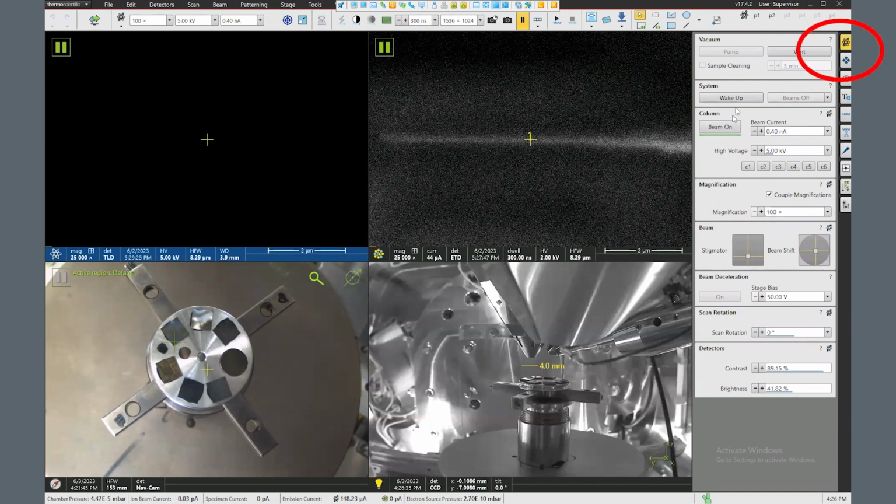So I come over here under the Beam Controls tab, and I'm going to turn the beam on. This green line here should always be green, basically telling you that the FEG module is active. You'll notice the beam on is now yellow, but still nothing is going on in the window. That is because of the pause icon up here in the corner. Most people undo this pause either by clicking on the icon itself or clicking on the acquisition button up here in the top bar.